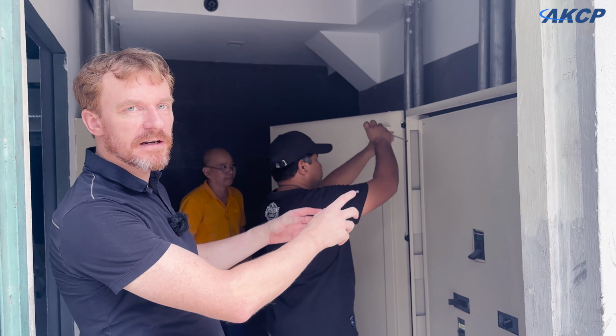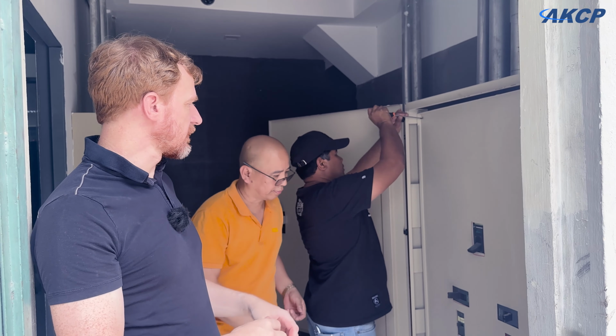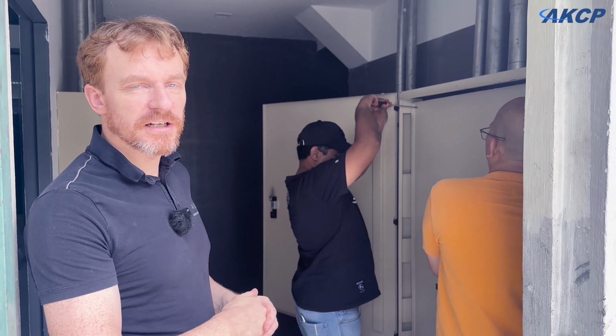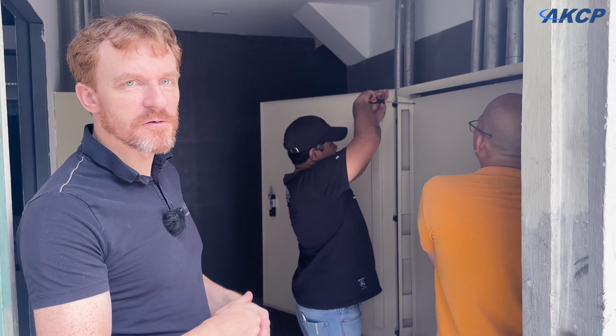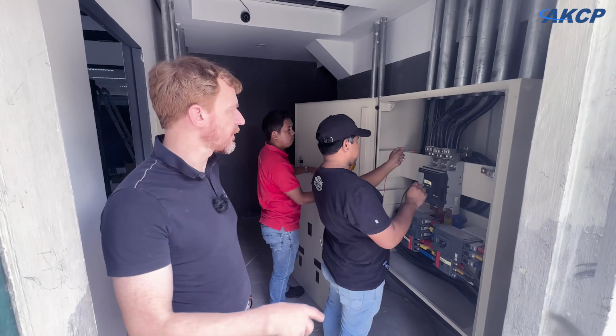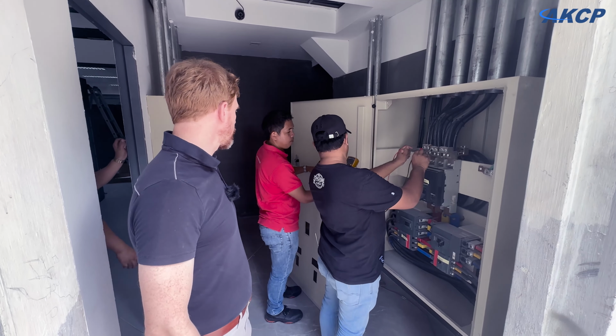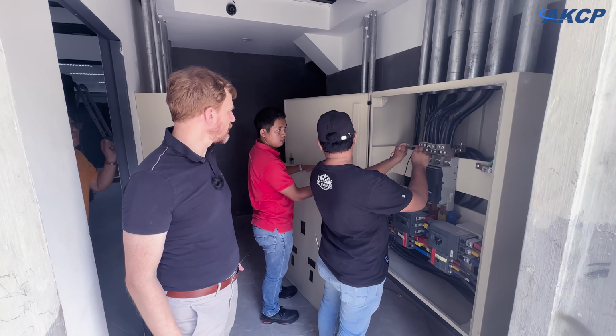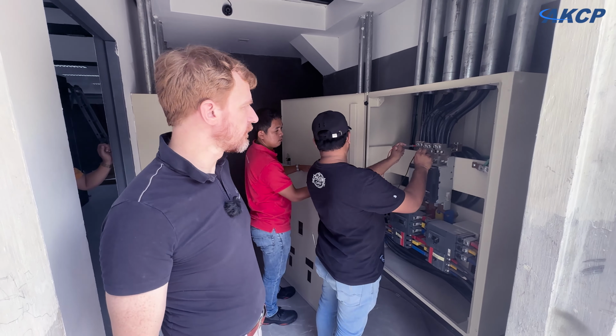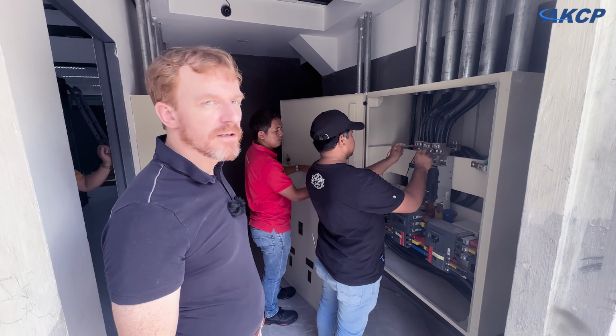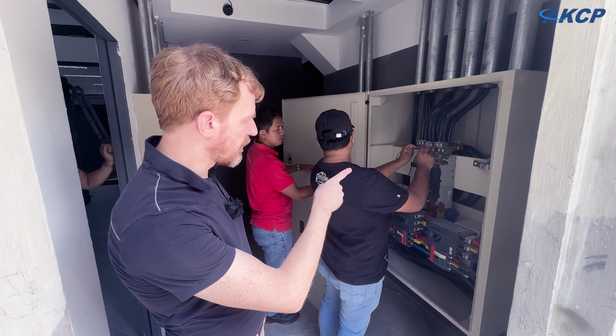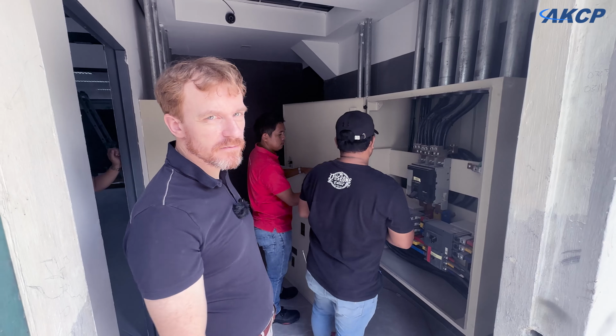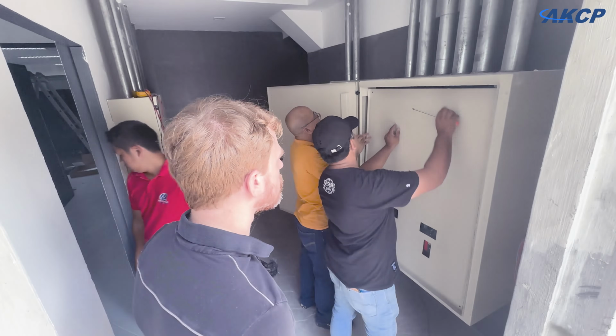So we'll just remove this panel so we can get access to the terminals, flip this on and check that we're getting 380 volts coming into the facility. Okay, so before we flip the breaker, we'll test the incoming side. We've got 381, 382. So we've got 380 volts now coming in. So we're ready to flip the breaker and connect that power out to the rest of the building.